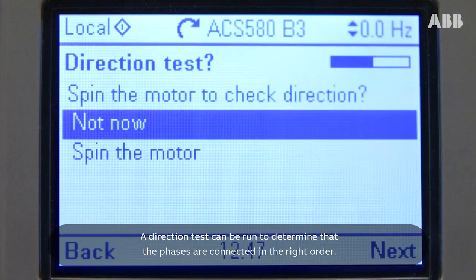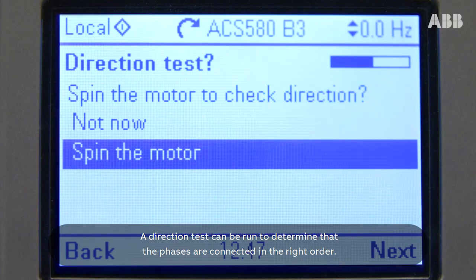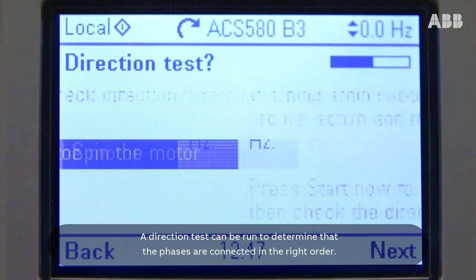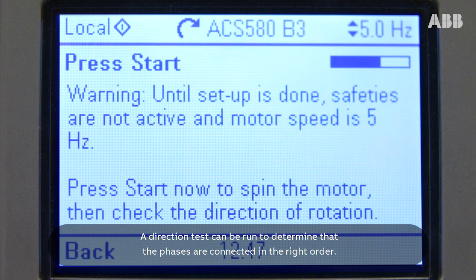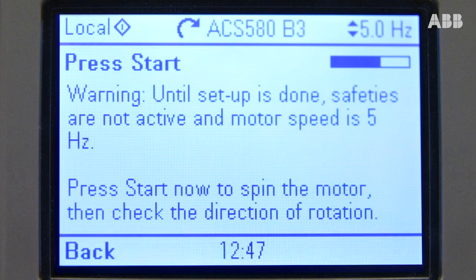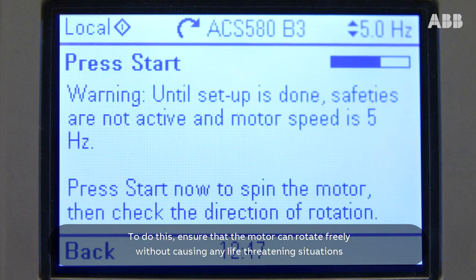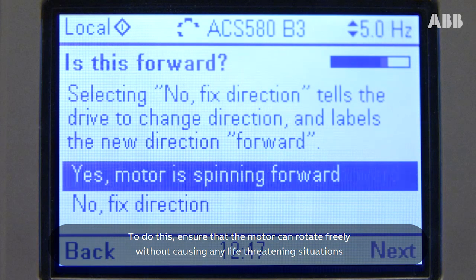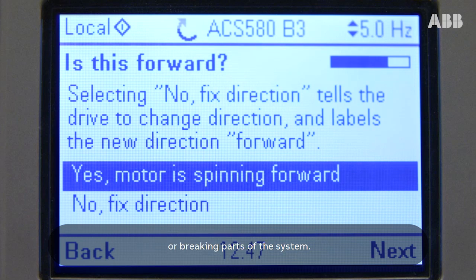A direction test can be run to determine that the phases are connected in the right order. To do this, ensure that the motor can rotate freely without causing any life-threatening situations or breaking parts of the system.